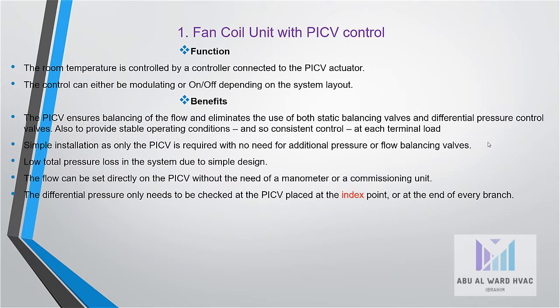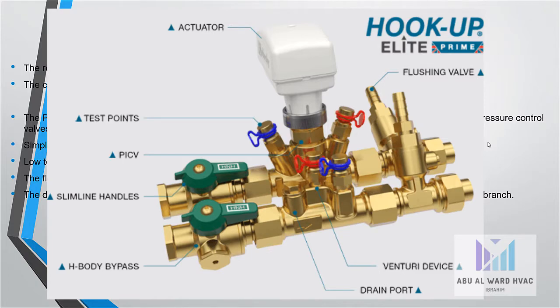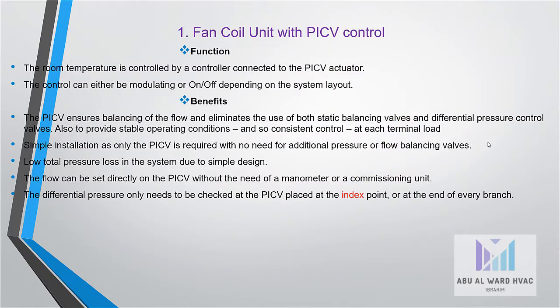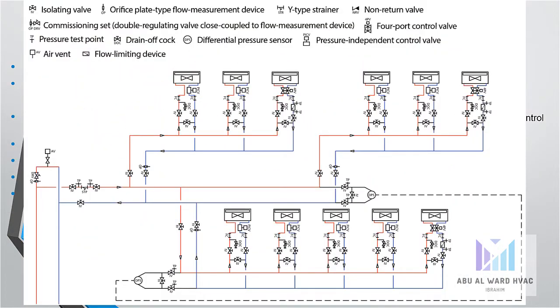The benefits: the PICV ensures balancing of the flow and eliminates the use of both static balancing valves and differential pressure control valves, also providing stable operating conditions and so consistent control at each terminal load. Simple installation, as only the PICV is required, with no need of additional pressure or flow balancing valves. Low total pressure loss in the system due to simple design. The flow can be set directly on the PICV without the need of a manometer or commissioning unit.